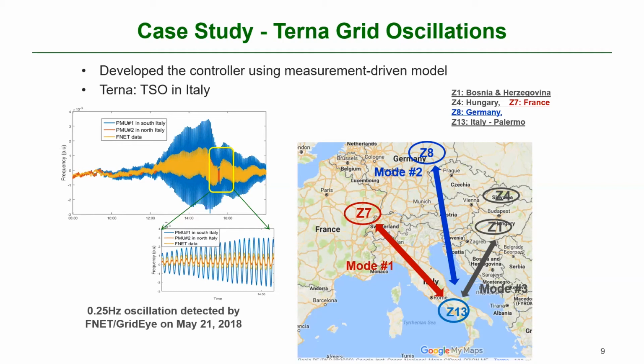So you can see here, we have observed oscillations in the European grid, and this part also shows they're actively pursuing ways to dampen the oscillation. So one of our initiatives is to use the measurement and observe the grid and provide damping oscillation designs for different projects. This is one of the Italian systems where we just went through a system study, and we did the hardware in the loop study. Basically, you're mimicking half of the reality, and then we're moving into the pre-installation phase.